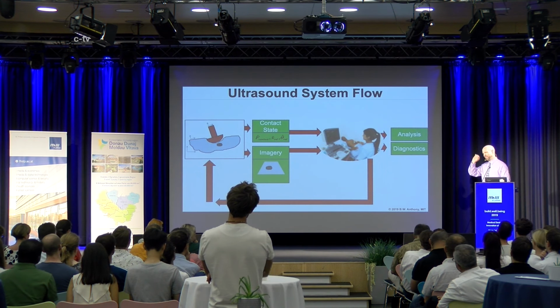And then I won't talk about the last bullet, but there's a fundamental problem, I'll call it that, in ultrasound imagers. When you're doing ultrasound, you send sound into the body, you're acting like a bat. It reflects off of boundaries, you receive sound, and the only thing you're actually measuring is time of flight, how long sound took to go in and come out. And you're converting time of flight into an image that has dimension because you've assumed a speed of sound. But the speed of sound in tissue is roughly 1,540 meters per second, but is highly variable based on the level of fat, the level of fibrosis, the patient themselves, and the tissue structure and tissue type that you're looking at. So there's a fundamental problem in the way that ultrasound systems are fundamentally constructed. We'll hold that and we'll talk about that offline.